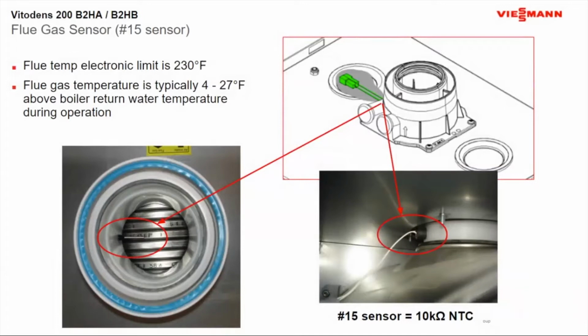A flue temperature sensor, also a 10K resistor. And as you can see, it goes off around 230 degrees. And typically our flue gas is normally anywhere from 4 to 27 degrees hotter than our boiler return water. So our flue gases are typically 4 to 27 degrees hotter than our boiler return water.